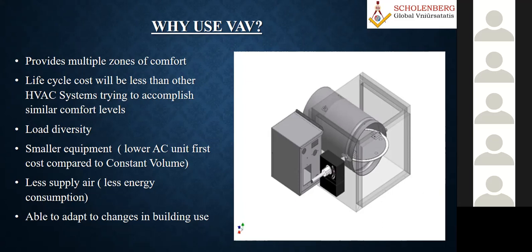In the same way, on the air conditioning side, if you have a variable load, your ventilation requirement, we should go for a VAV system, and that helps you save almost 30% of the energy compared to the constant volume system. 30 years ago, everybody was using a constant volume system, but later the technology advanced, and we started using the VAV system. It helps with multiple zones, and the life cycle cost is also much less. You have a lot of load diversity, and these are some of the advantages of the VAV system.